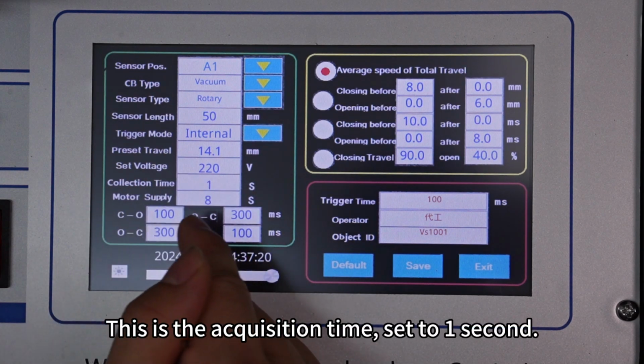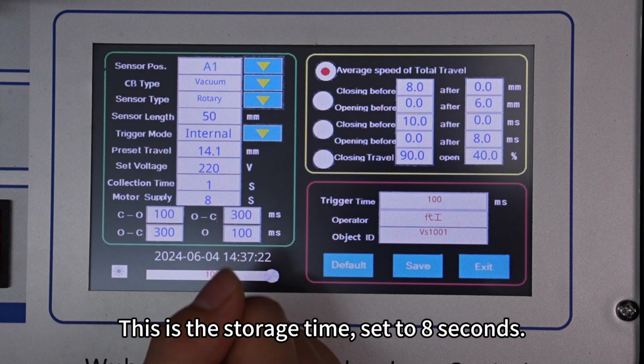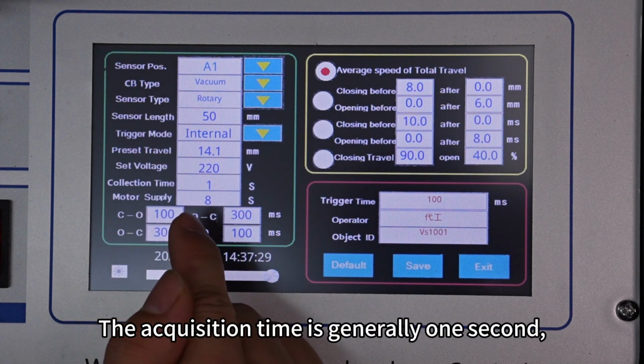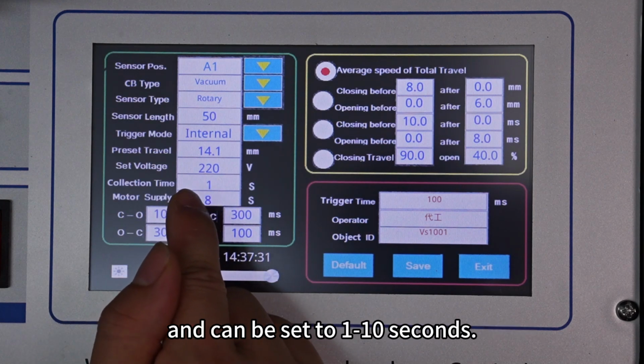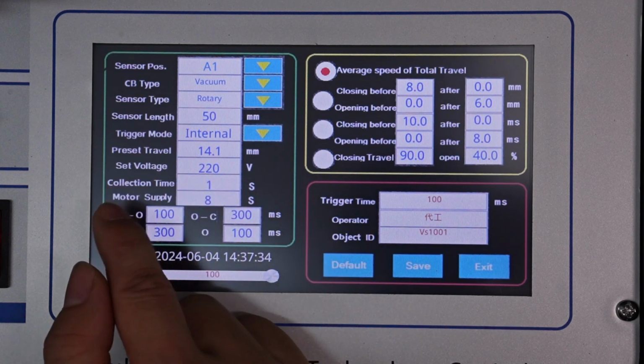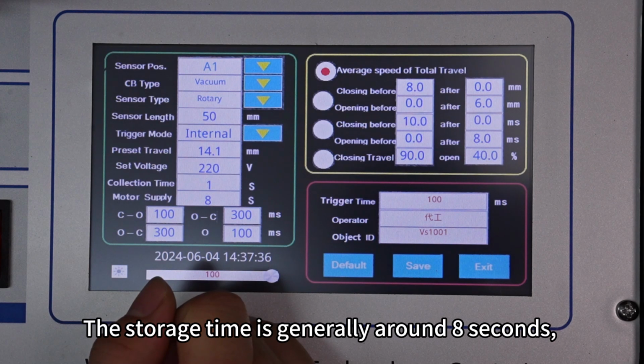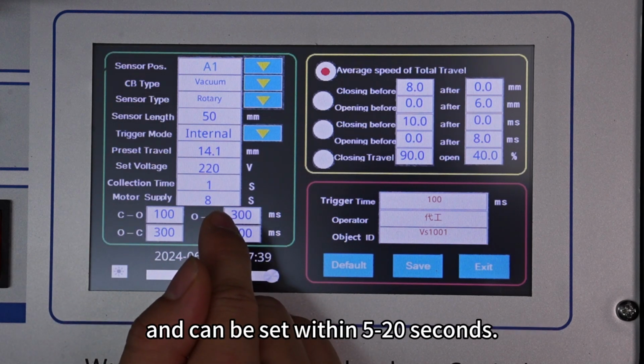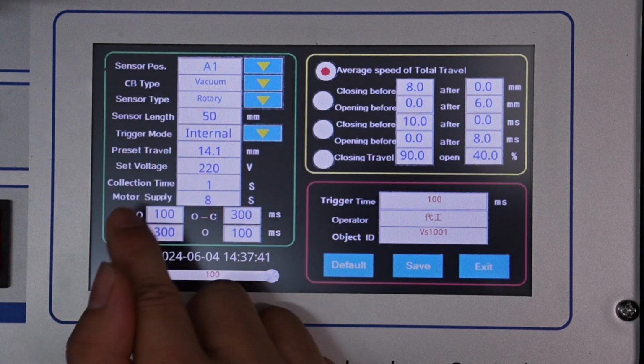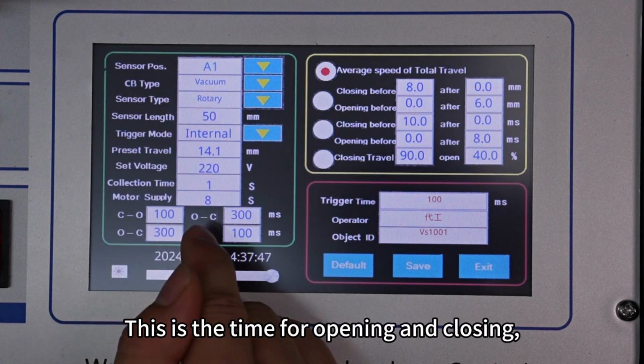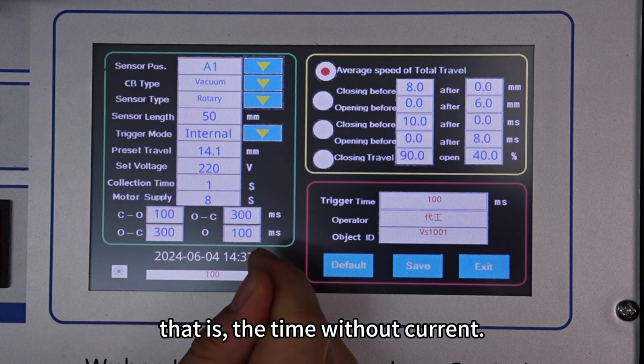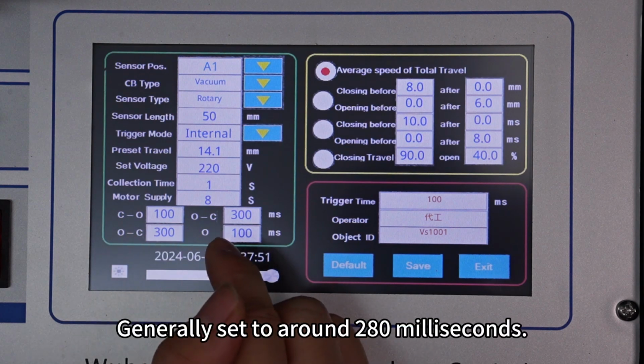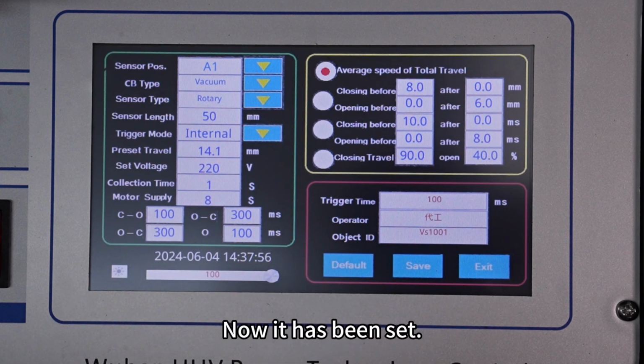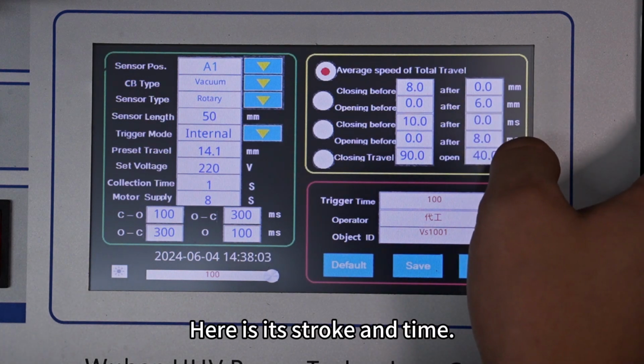This is the acquisition time, set to 1 second. This is the storage time, set to 8 seconds. The acquisition time is generally 1 second, and can be set to 1 to 10 seconds. The storage time is generally around 8 seconds, and can be set within 5 to 20 seconds. This is the time for opening and closing, that is, the time without current. Generally set to around 280 milliseconds. Now it has been set. Here is its stroke and time. This is closing.